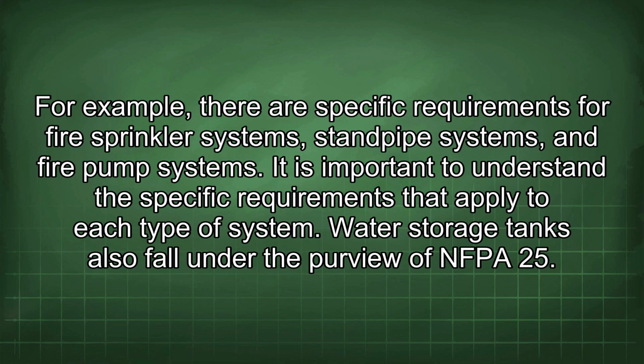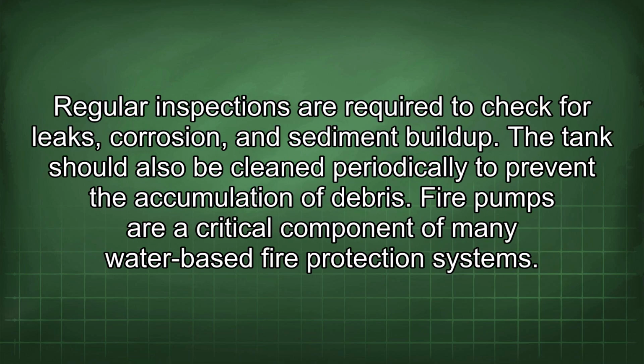Water storage tanks also fall under the purview of NFPA 25. Regular inspections are required to check for leaks, corrosion, and sediment buildup. The tank should also be cleaned periodically to prevent the accumulation of debris.